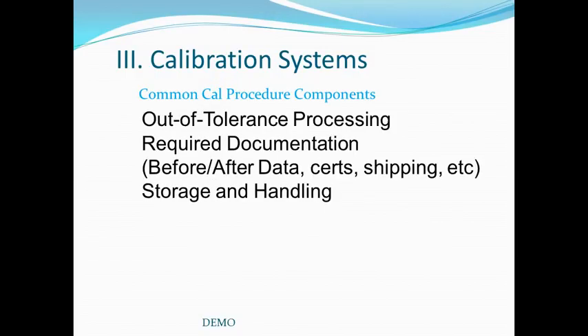Other calibration components would include how to take care of out-of-tolerance processing. If you find a value out of tolerance, how do you report that? This should have some procedure in the calibration procedure or reference to some standard operating procedure outside of the calibration procedure. Also, any required documentation, such as before and after data, should be included, any certs, shipping instructions, and so forth. Also, storage and handling should be included as a procedure component.